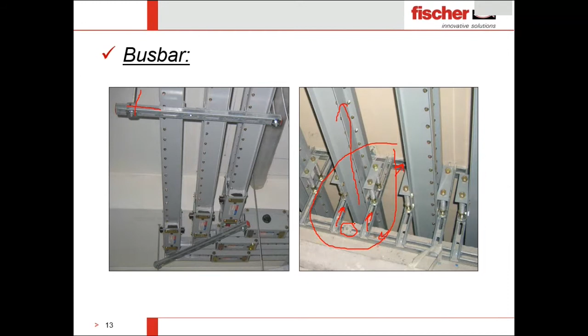Here you have one main channel, and another channel forming the main beams, then secondary beams for each bus bar, one before and one after. The bus bar is supported in the channel like this, allowing the riser to go this way, which is the most common method used in the Middle East. This is then anchored somehow to concrete, and we'll see in a few slides what's required for the design.